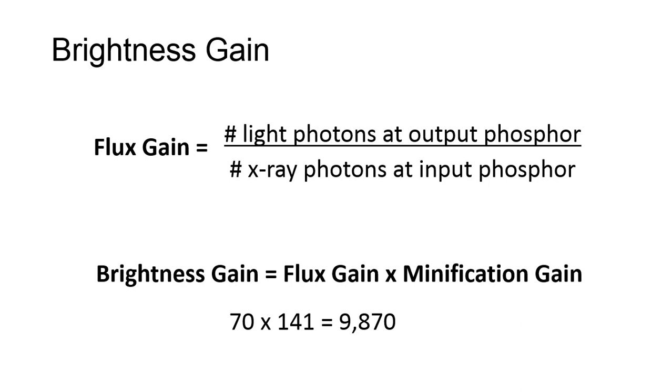To find brightness gain, you would multiply the flux gain, which was 70, by the minification gain in the previous example of 141. The result is that the total brightness, or brightness gain, is 9,870, meaning that the light at the output is 9,870 times brighter than the original brightness at the input phosphor.